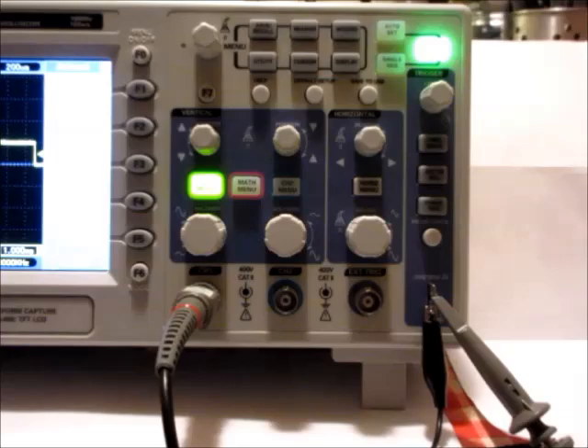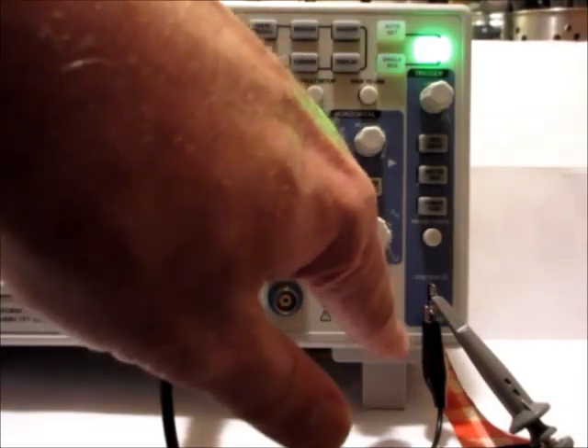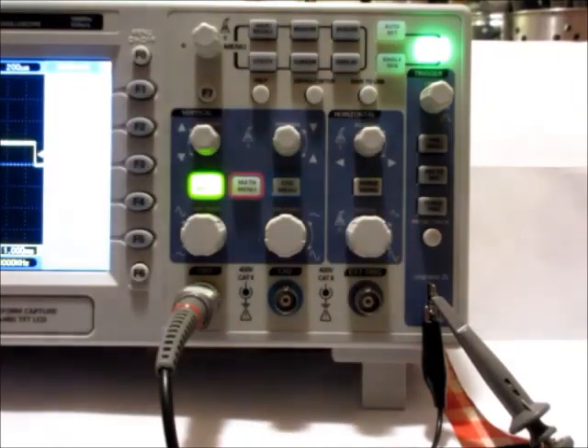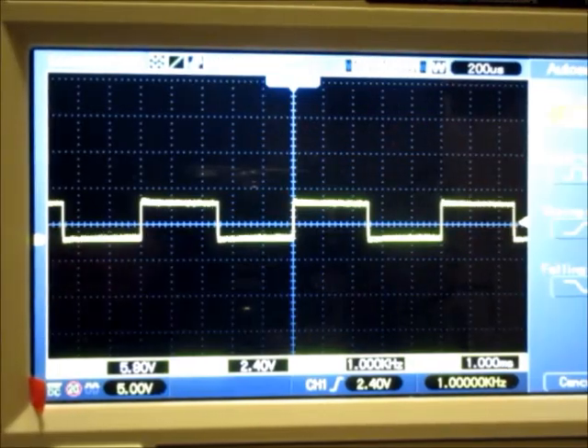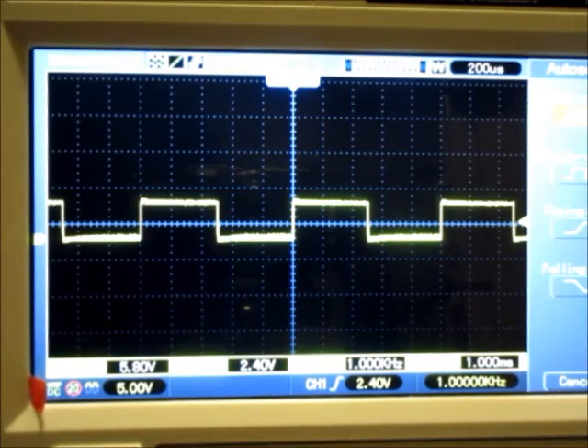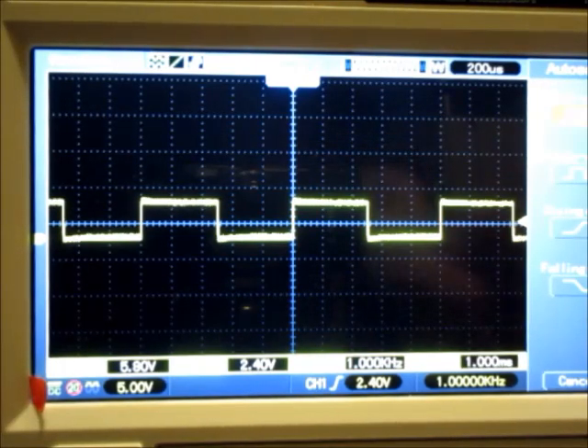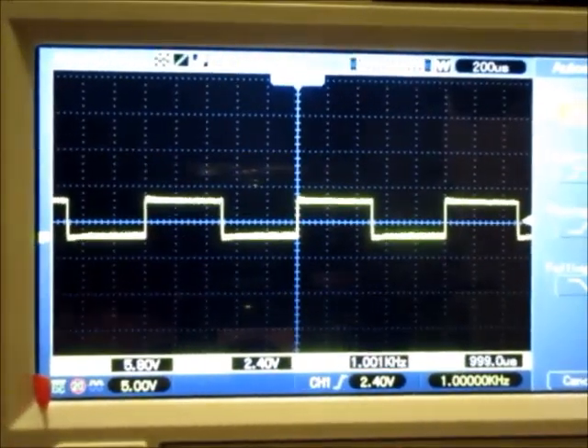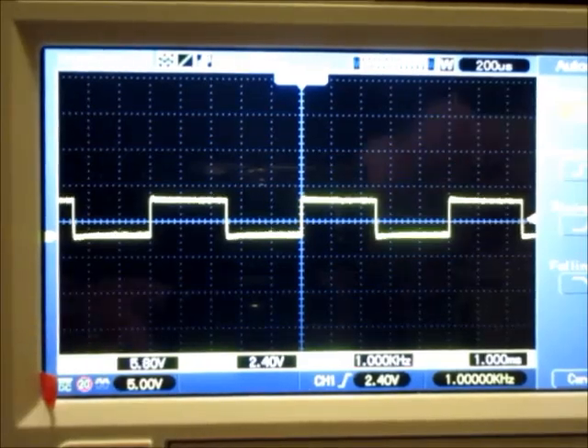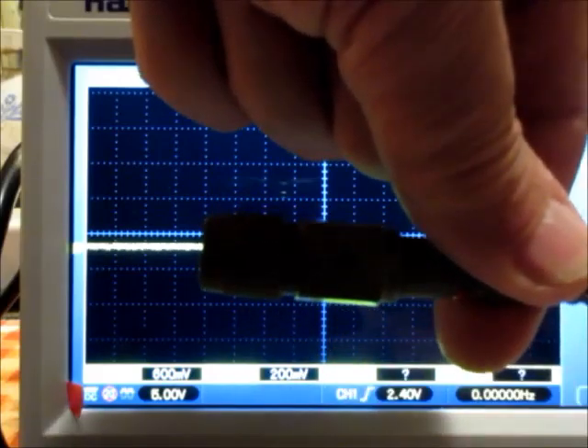Here's a modern oscilloscope, and you can see that it's got its own 1,000 hertz square wave right on the front panel. And most oscilloscopes are like that today. But sometimes you have to use an external oscillator to compensate the older scopes. Here is a properly compensated modern scope. But if I have to adjust this, the adjustment is to be made in the probe. In this one, the adjustment capacitor is right here. So if I had to make any compensation, that's where it is.